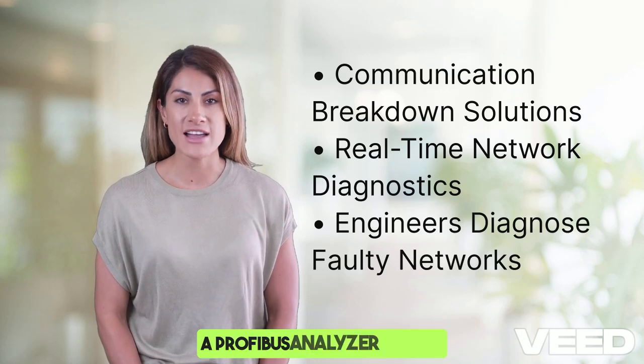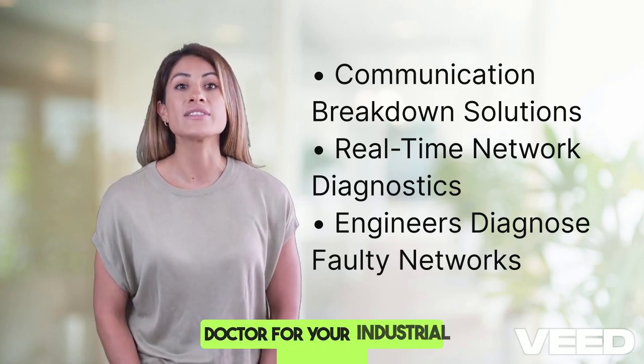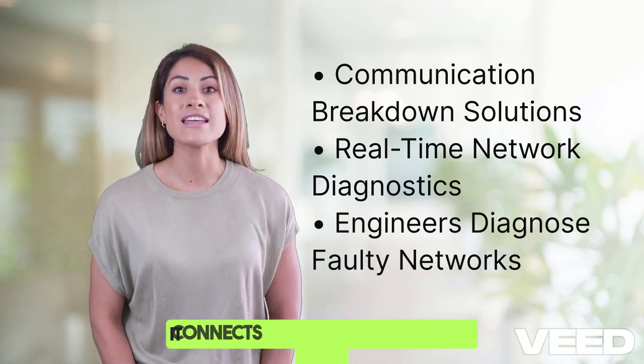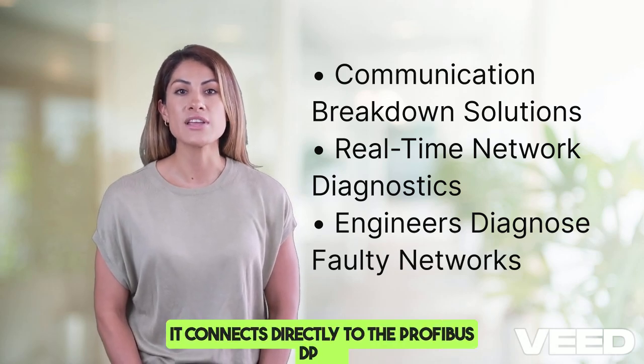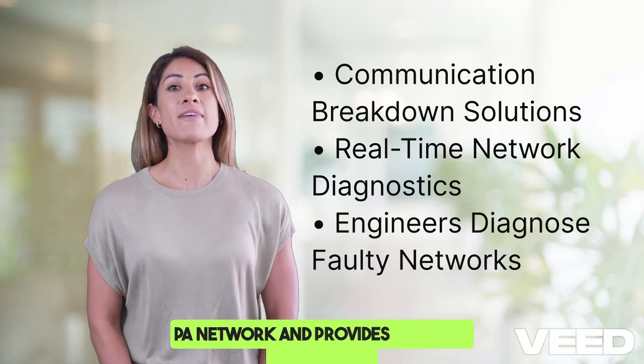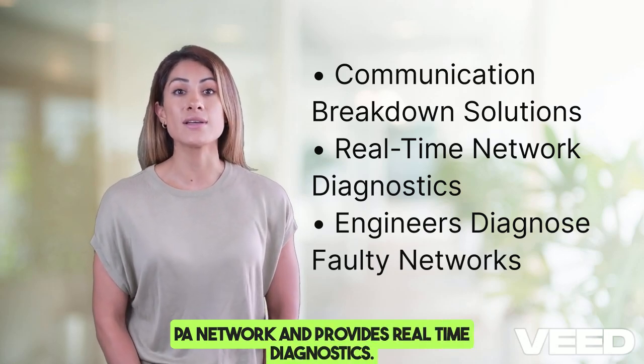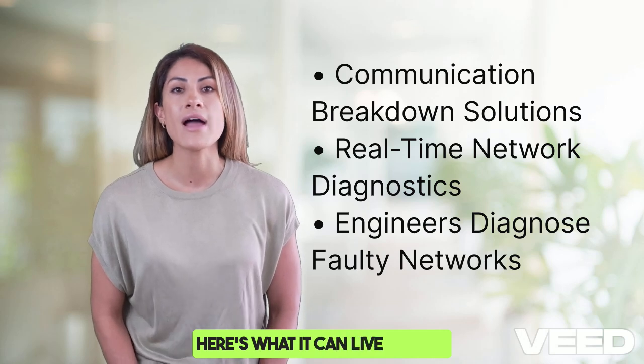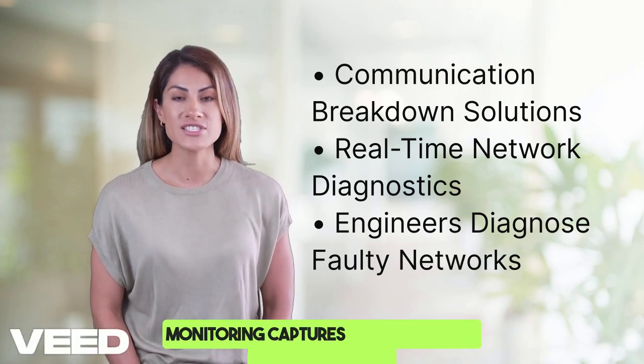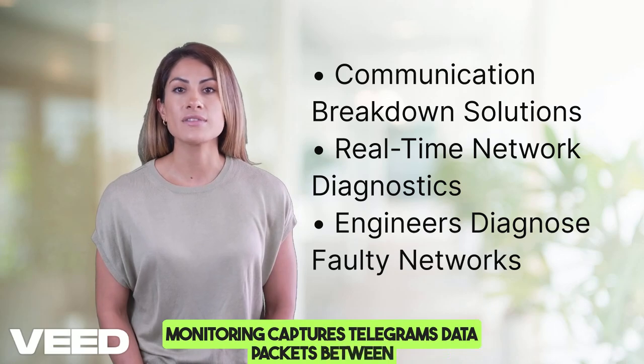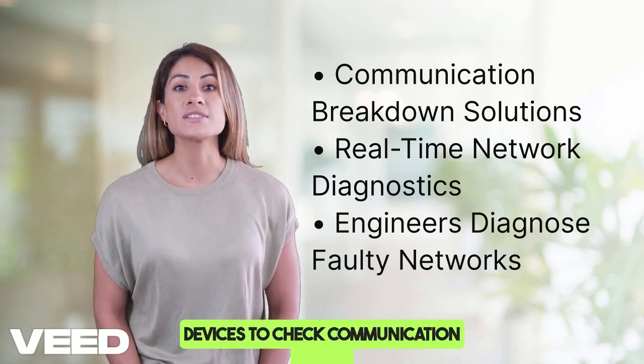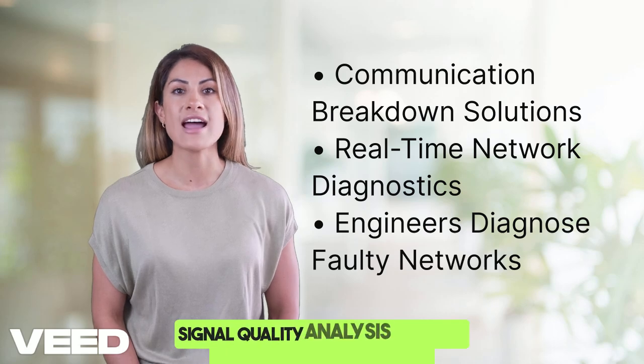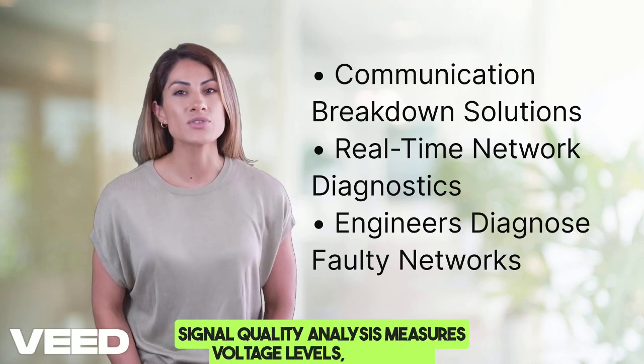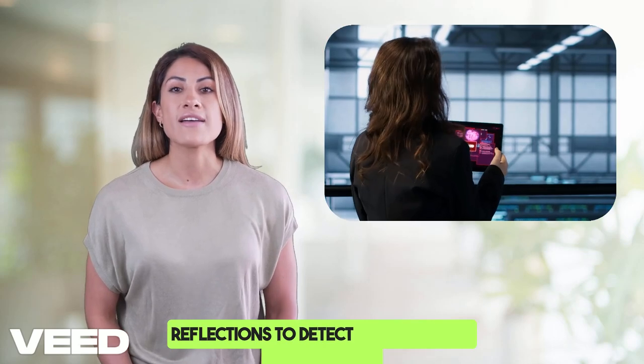A Profibus Analyzer is like a doctor for your industrial network. It connects directly to the Profibus DP or PA network and provides real-time diagnostics. Here's what it can do. Live traffic monitoring: captures telegrams, data packets, between devices to check communication status. Signal quality analysis: measures voltage levels, noise, and reflections to detect bad cables or terminations.